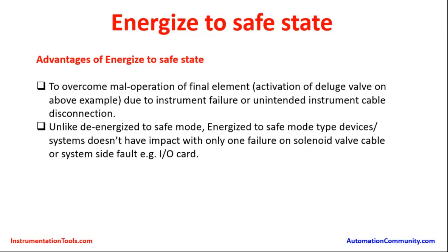The advantages of Energize to Safe State: it helps overcome mal-operation of the final element — for example, accidental activation of a deluge valve due to instrument failure or unintended instrument cable disconnection. This Energize to Safe State principle helps overcome mal-operation of the final element. Unlike the de-energized safe mode, Energize to Safe mode devices and systems are not impacted by a single failure on the solenoid valve cable or system side fault. If there is a cable cut or any system side fault such as an IO module failure, it is not harmful.